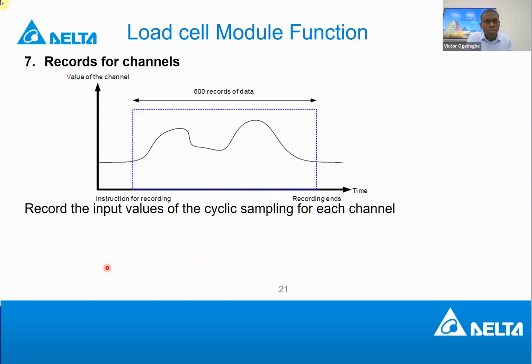Or, for example, your application is a filling application, where you are filling a bottle or a package. If you fill a package more than what is supposed to be there, this bit could trigger, indicating that the sensor is measuring a value that is more than what we want. Then you can take that package out, put it aside, and solve the problem. So this gives you a flag when what is measured is more than the maximum that should be measured. Seven is record for channels.